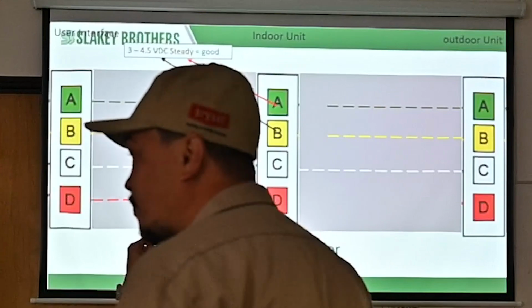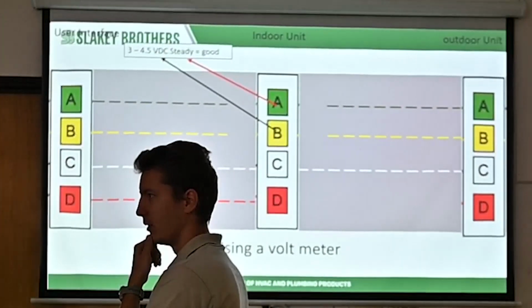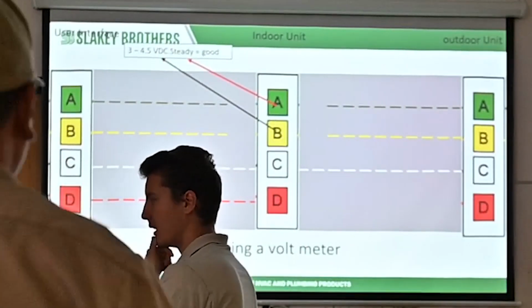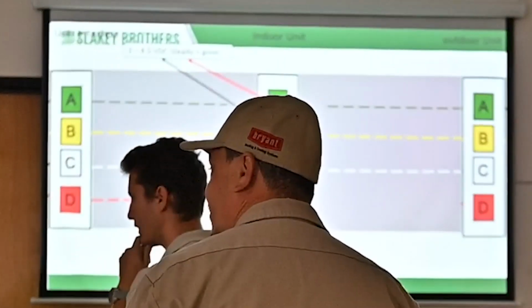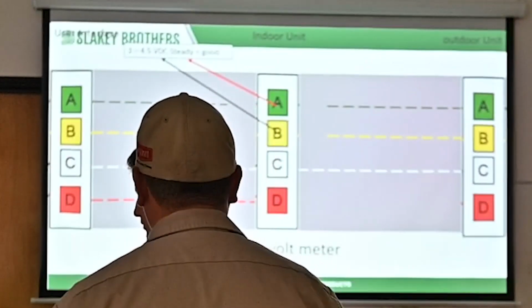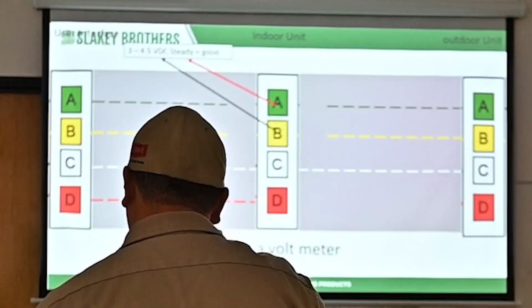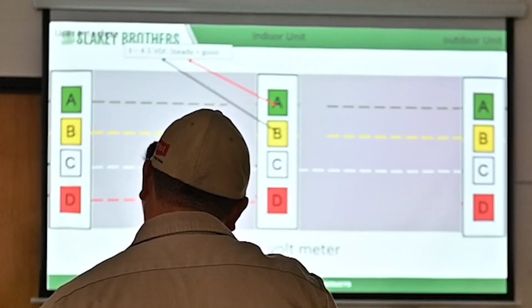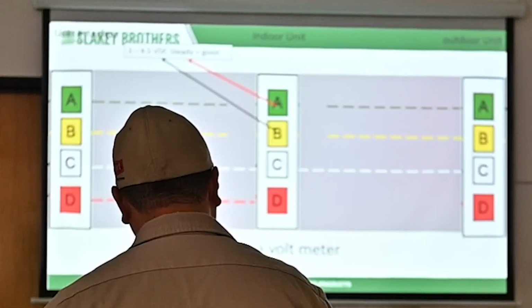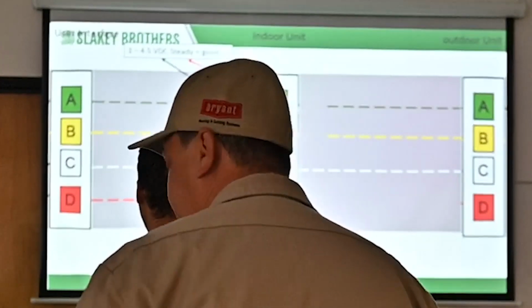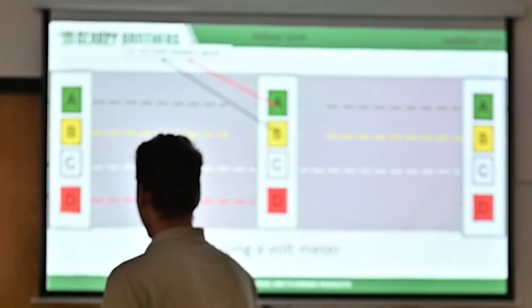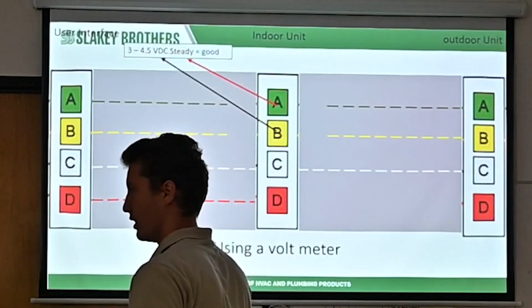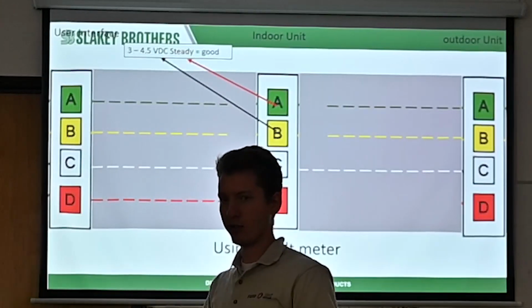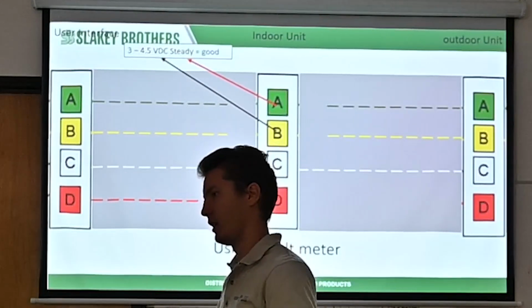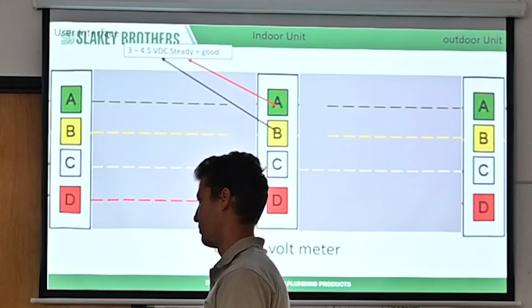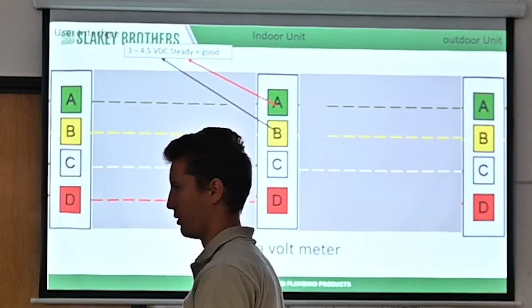And it worked beautifully. Then the outdoor unit was having the same issue, but the outdoor unit always had a problem because the wire was messed up from rats. We had to run a whole new wire for the outdoor unit as well. But yeah, when you're having a problem like that, in my case, exactly the same. I tried to find what the problem is. I disconnected the wire and checked it with the voltmeter, everything is good. But after that, I ran a new wire from the furnace to the outdoor unit, and everything works fine. In this case, we replaced the whole wire.